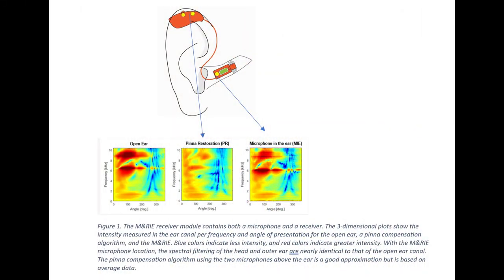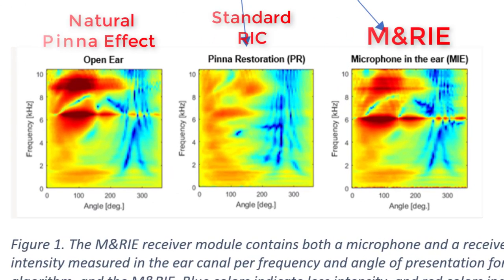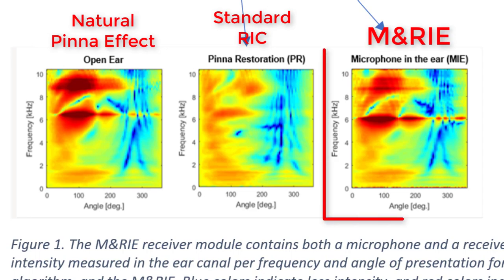Even though manufacturers try to program in correction factors to replicate the natural pinna effect, because they're taking the hearing aid out of the ear and putting it behind the ear, it's never as good as the real thing. Take a look at these measurements of an open ear canal versus a traditional receiver-in-canal hearing aid trying to recreate the natural pinna effect, and finally a Microphone And Receiver In Ear — otherwise known as the M&RIE. You can see that the pinna effect was maintained much better with the M&RIE microphone inside of the ear canal, which can help you localize sound better, perform better in background noise, and make things sound more natural.